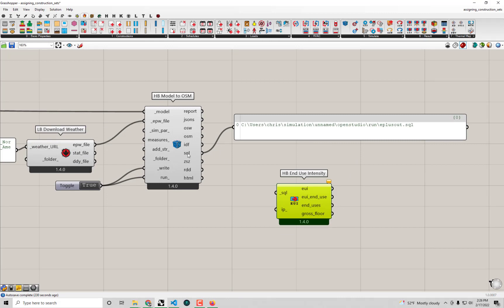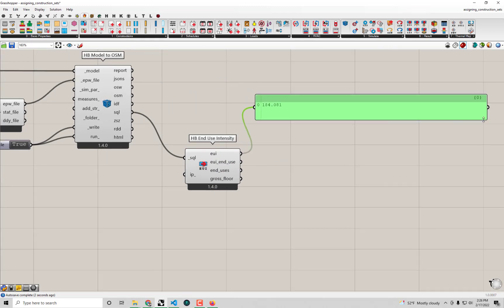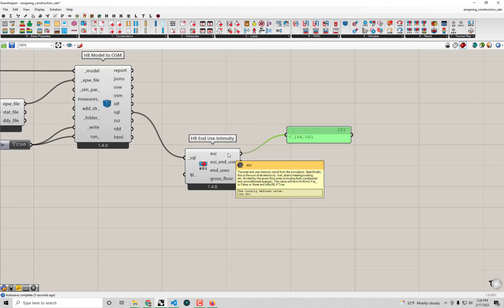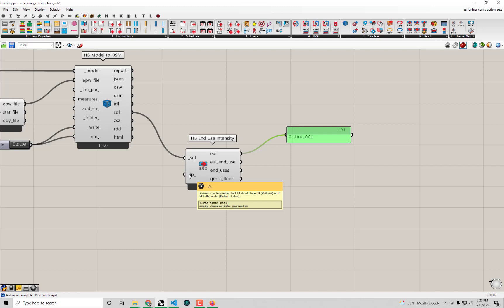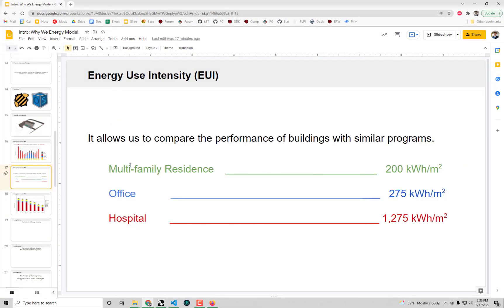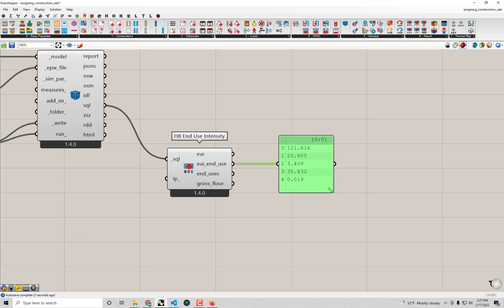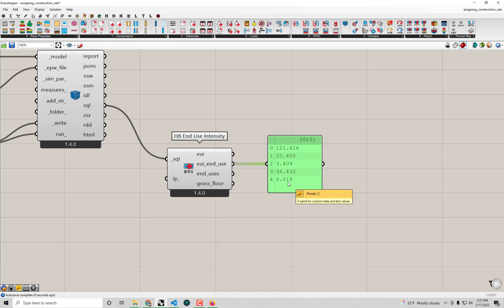I'll connect my SQL file from the single family home simulation to the HB End Use Intensity component. The component runs immediately. We get an EUI output — hovering over the input confirms it's in kilowatt-hours per square meter by default, which can be changed to kBtu per square foot by setting the IP input to true. Our result is about 184 kWh per square meter, which is in line with the typical U.S. residence at around 200 kWh per square meter, giving us confidence our model is on the right track.